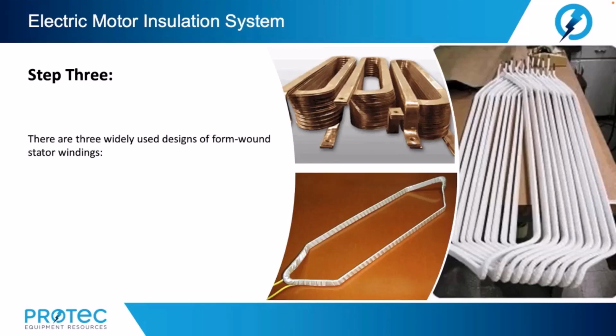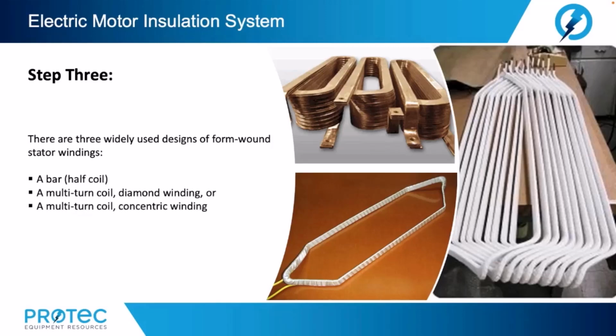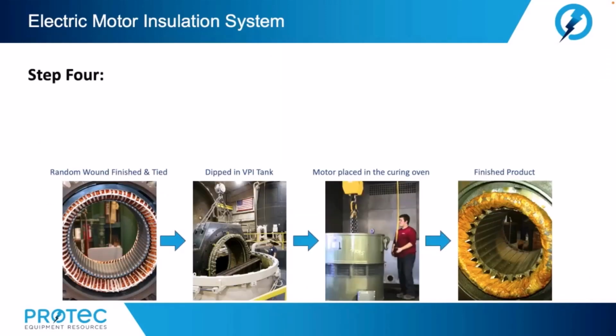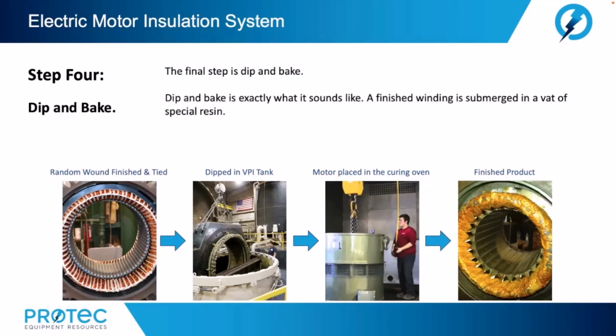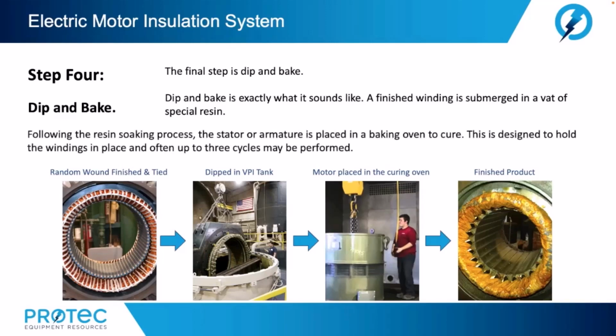There are three widely used designs of form wound stator windings: a bar or half coil, a multi-turn coil diamond winding, or a multi-turn coil concentric winding. Now, step 4, dip and bake. The final step is called dip and bake, and it is exactly what it sounds like. A finished winding is submerged in a vat of special resin. Following the resin soaking process, the stator or armature is placed in a baking oven to cure. This is designed to hold the windings in place, and often up to 3 cycles may be performed.